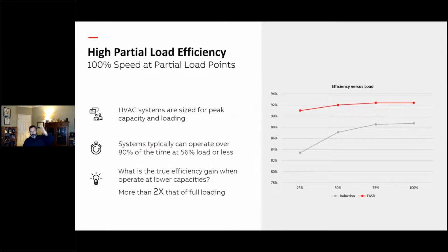I've been talking about flatline efficiency performance, and here it is. This is actual lab testing data. Yes, it's prettied up to put into a presentation, but it is based on measured lab dynamometer testing of an induction motor versus the FASR design. This is at 100% speed and partial load points. Systems are designed for peak capacity and loading, but they're sometimes run at partial loads. This would be more like a constant CFM system that's running at a fixed speed, but the loading is variable. You can see it's up to 2 times the efficiency gain at 25% loading than at full load and full speed.